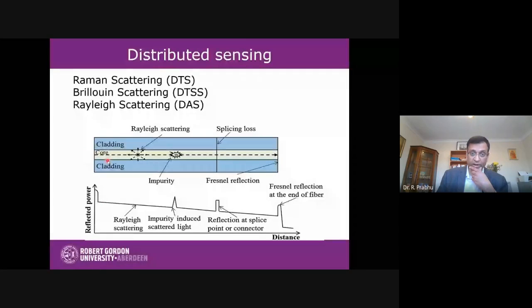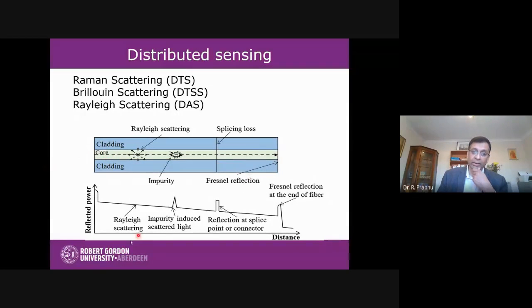You can see the long optical fiber: as the light propagates from one end to the other, based on impurities or non-uniformities in the fiber, there will be a reflected spectrum in the time domain, backscattered light. That can be correlated to distance if the refractive index of the core is known. You can see continuously decreasing Rayleigh scattering, mainly due to the loss of the fiber, with impurities resulting in small peaks like this, and reflections due to splicing. OTDR, optical time domain reflectometers, can be used for monitoring the backscattered light and predicting what is happening along the fiber. These are the basic principles used for distributed sensing with optical fiber.